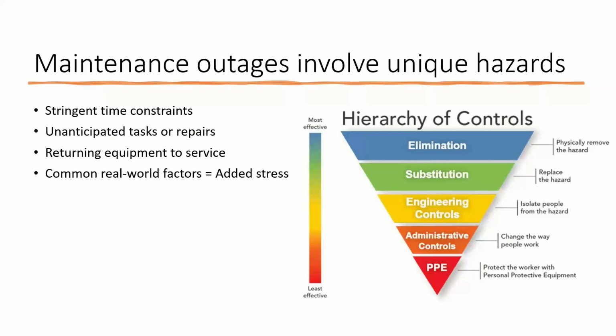The important thing is that we think about this chart as a system. The administrative controls need to work in collaboration with everything else. They set the pace for making sure you have the right arc flash labels in place, that a study has been done, that you're taking proper lockout, tagout procedures, and that those are in place for shock prevention. They've got the PPE you need for shock and arc flash, and you follow the steps required for your location. So think about that as a system and how it all works together.